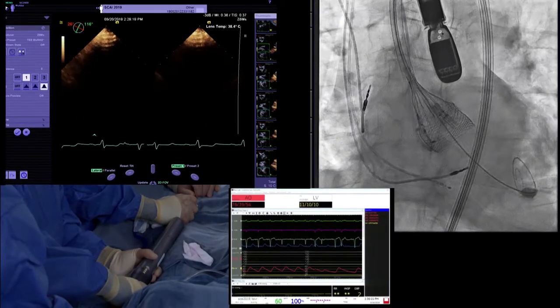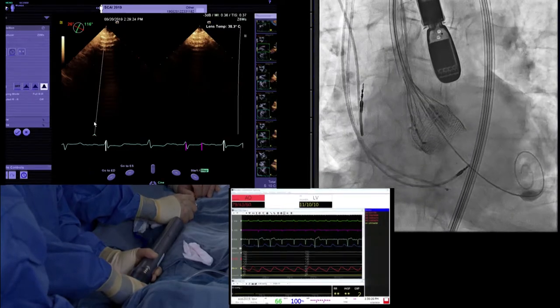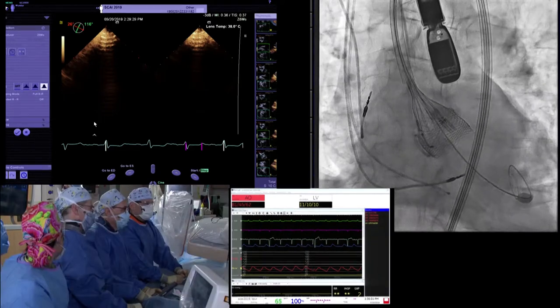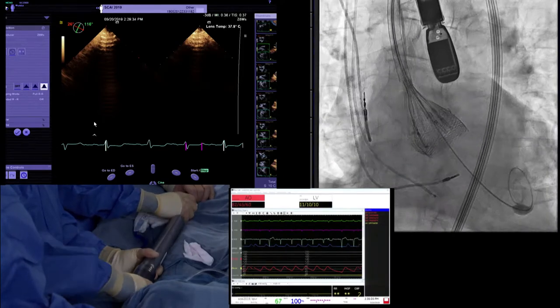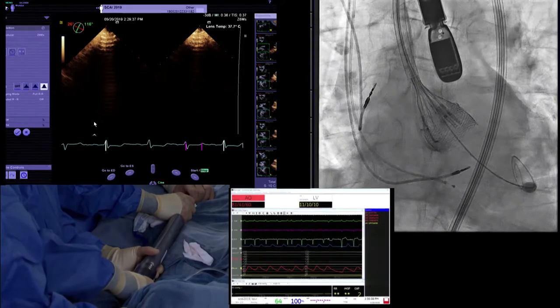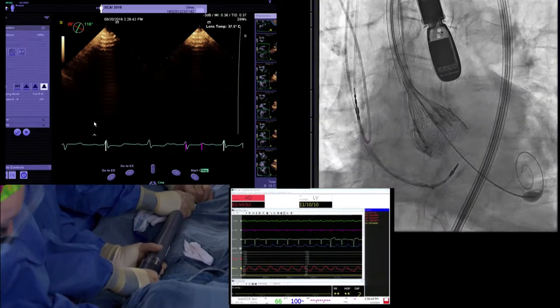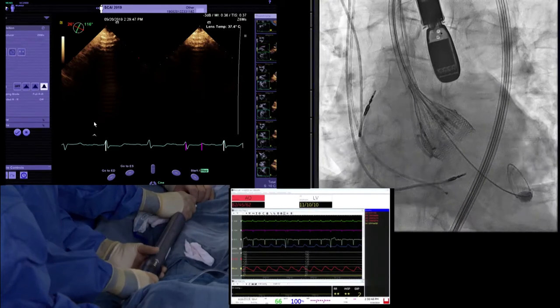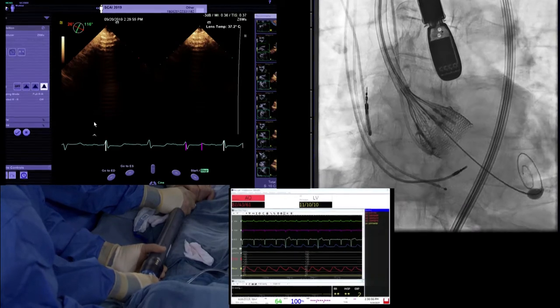You can see the buckles and posts are very close together. I like the way the frame looks — I like the frame density. You have to be a little careful here because once it locks, they open back up again, so you just need to see them touch. I think we're at lock on at least two of the three. I'm giving quite a push-pull to make sure the valve does not move.